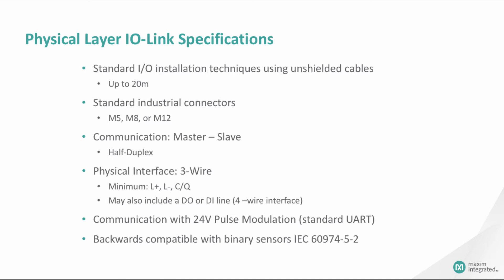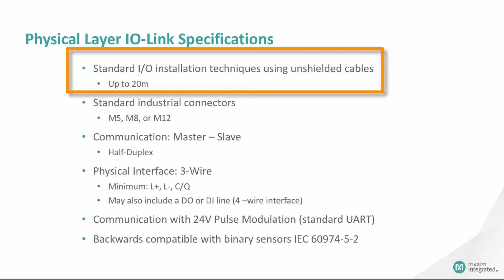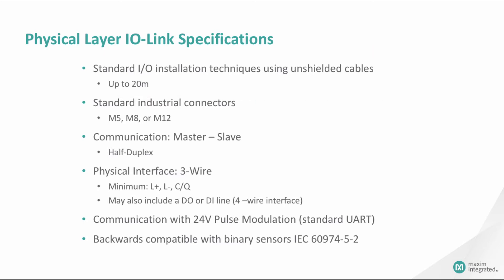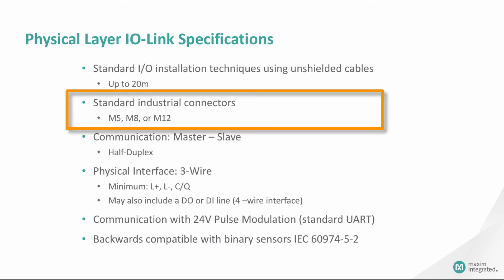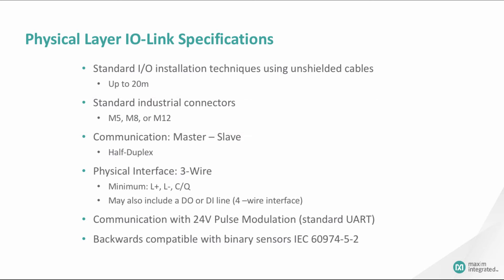The IO-Link standard states that IO-Link communications are limited to a distance of 20 meters using unshielded cables. IO-Link connectors are already in wide use in industrial systems. M5, M8, and M12 connectors are allowed, with M8 and M12 most predominant.